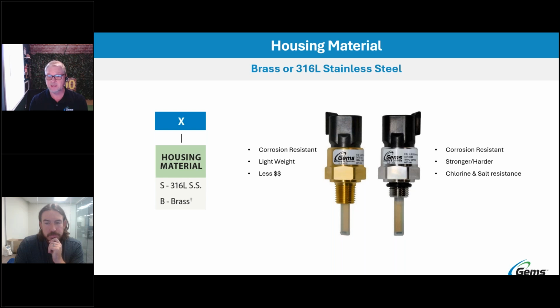The first option is the material housing. We have two available: 316L stainless steel and brass, both corrosion resistant. You might pick brass because it's lighter weight and has a slightly lower cost, whereas stainless steel is a stronger, harder material with additional resistance to things like chlorine and salt. There's also a galvanic interface issue that may come up—some metals do not mate well with other metals, so you may have to pick one over the other because of that.